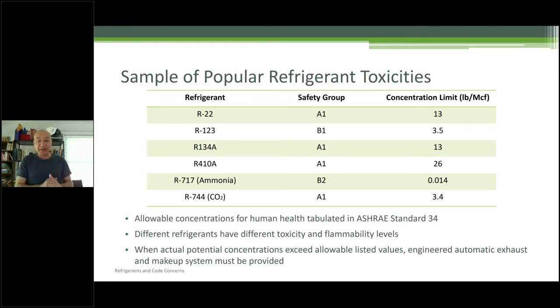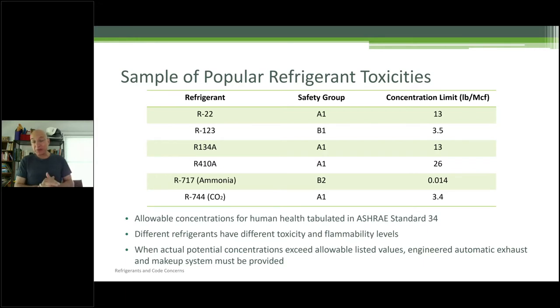You can see right away why 410A is a great refrigerant — it's A1, not toxic, not flammable, and it allows 26 pounds per 1,000 cubic feet. That essentially allows VRFs to be used without much concern. Ammonia is different — that's a B2. There are some ammonia plants out there, ice skating rinks, certainly on an industrial level, but you've got to be very careful. Look at the concentration limits — very low, 0.014.